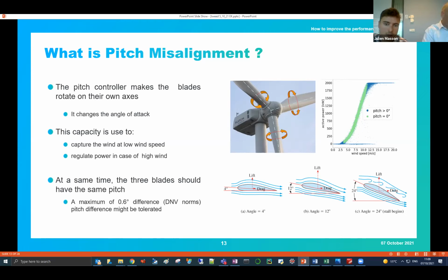The pitch is used, as I said, to adjust the angle of the blades relative to the wind velocity seen by the blade. So it's linked with the angle of attack, and so the lift, and so the production. Basically, the pitch is set to 0 degrees during most of the operation time of the turbine. The angle is set to a higher value when we reach the rated wind speed, and so we brake the turbine and set the pitch to keep the power at the maximum power, the rated power, here for example in megawatts.